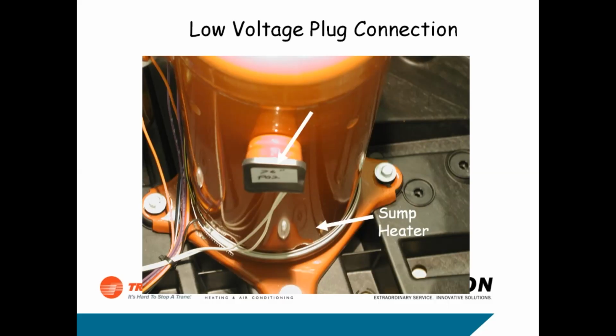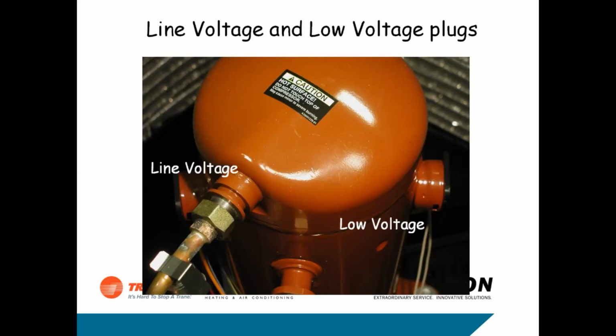The low voltage terminal strip on the compressor looks like this. It's got the two white wires going into it, and that's the 15 to 27 volts DC. And then the line voltage, of course, is on the other side. Again, if you want to ohm out the compressor, it ohms out the same as a single phase compressor, just like we talked about earlier. And the low voltage ohms out as the low voltage side.